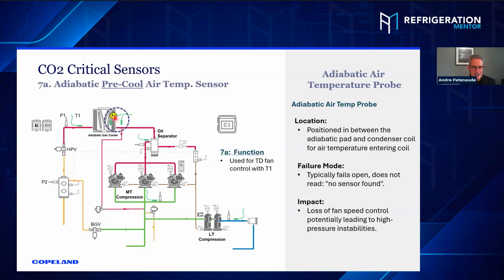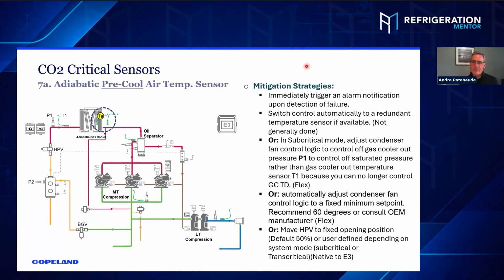The difference between your 7A and your T1 is a temperature difference when they're not operating at full speed and you're modulating fan speed. So if you lose that 7A sensor, your loss of fan speed control could potentially lead to pressure instability, right? So how do we mitigate that? Immediately, if you get a 7A failure, an open contact, trigger an alarm notification. Now, it says switch automatically to a redundant temperature sensor, but that's generally not done. I asked the gas cooler guys. They said, no, we only put one in there. So even though it is a strategy, it's not generally done. Just footnote that.